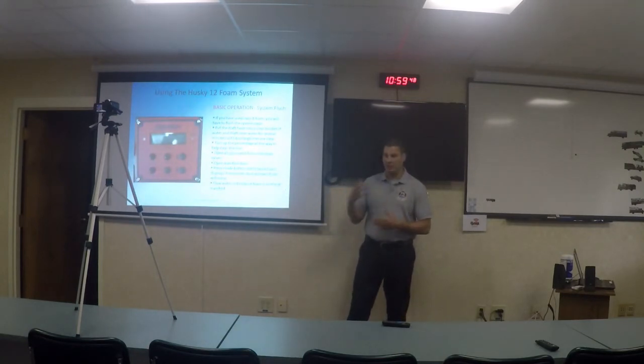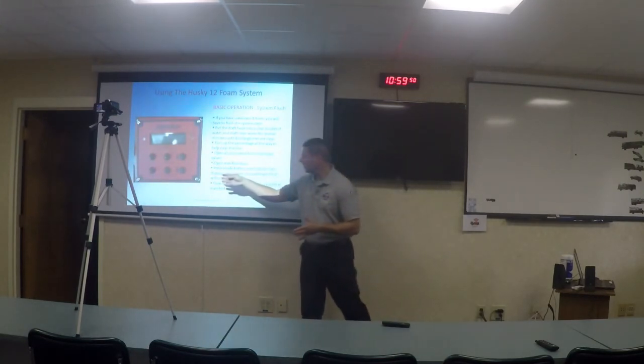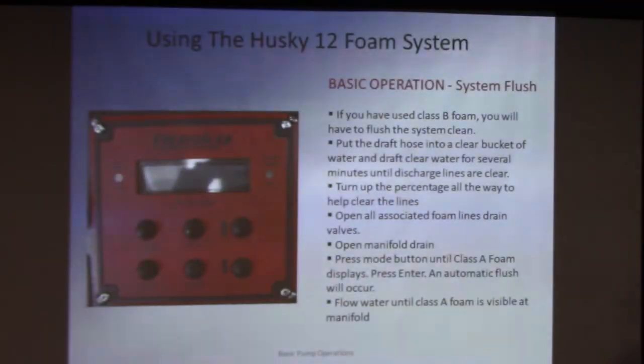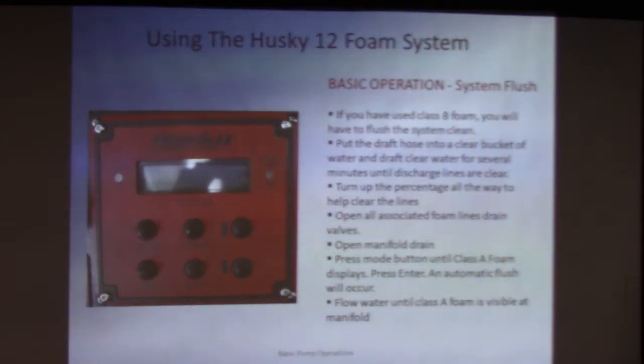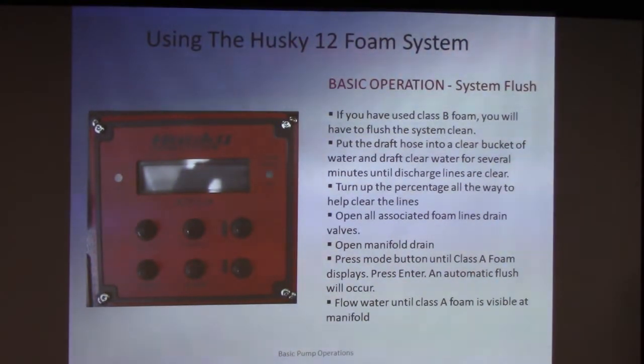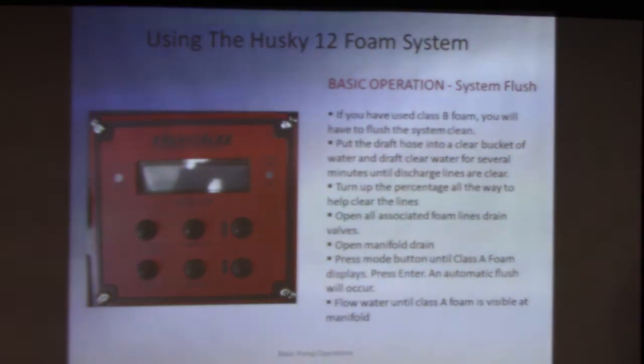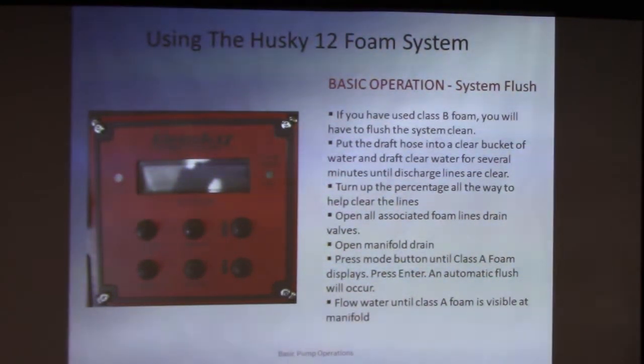There's also a manual flush you can do by going through this. You would open the manifold drain — the main manifold drain — and the manual flush valve drain, which is a knob. Anytime some sort of flushing is going on, the flush valve drain should be open. It's a little quarter-turn knob on the side. For Class A it's not necessary; for Class B it is.